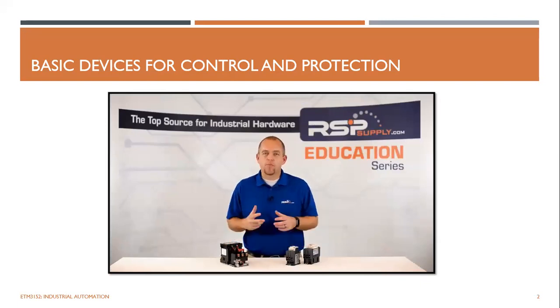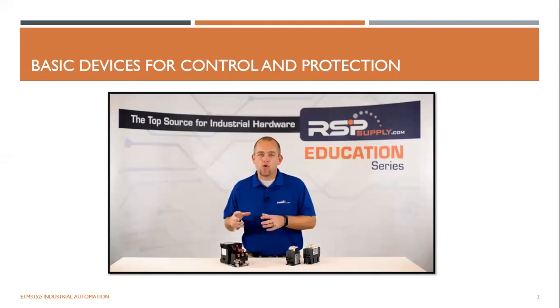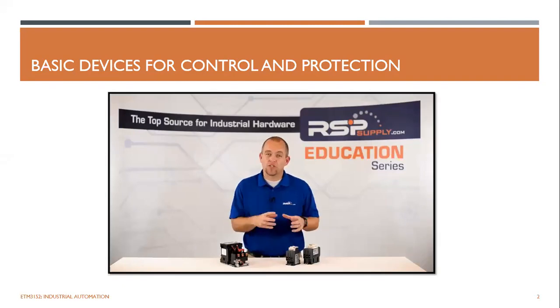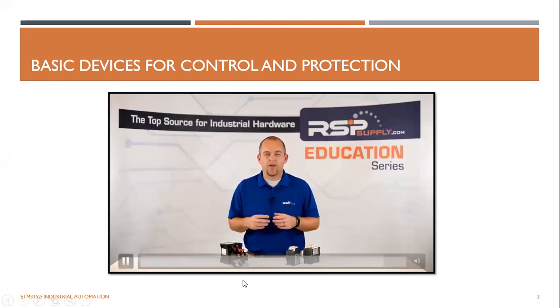Then we want to make sure that we match up our motor with the specific type of motor starter that we purchase. In order to do this, we need to know the motor voltage. We also need to know the motor full load amps or horsepower. And we also want to make sure we know what we need our coil voltage to be. And knowing these things, we can better determine what type of motor starter to buy.